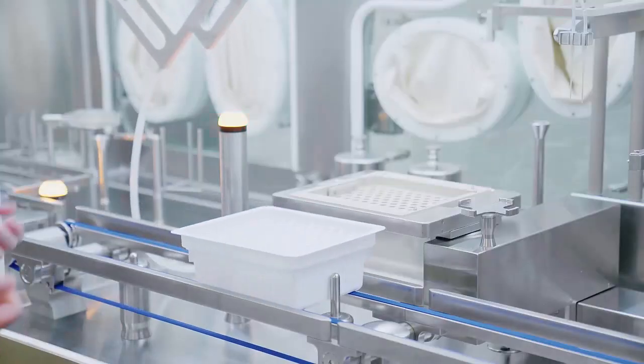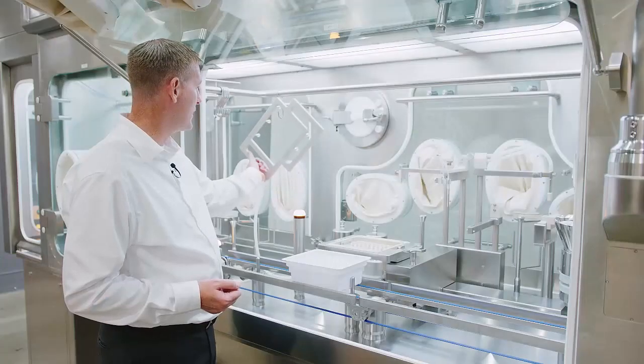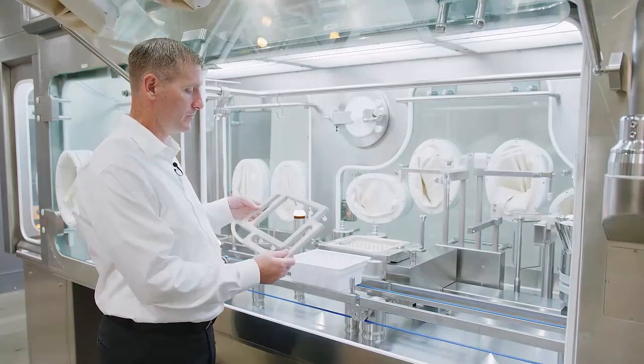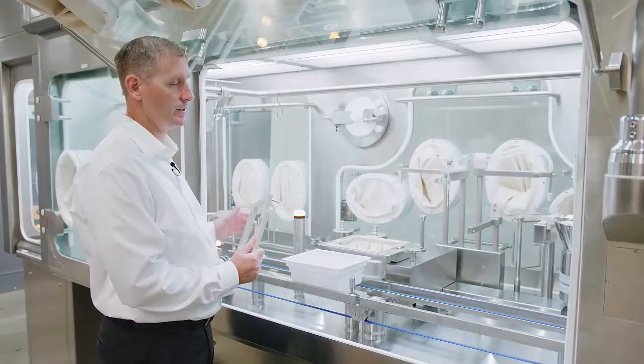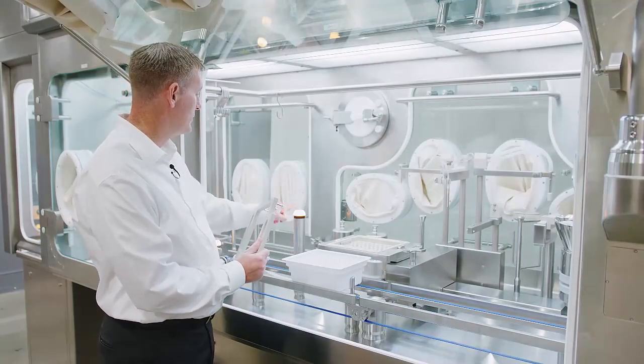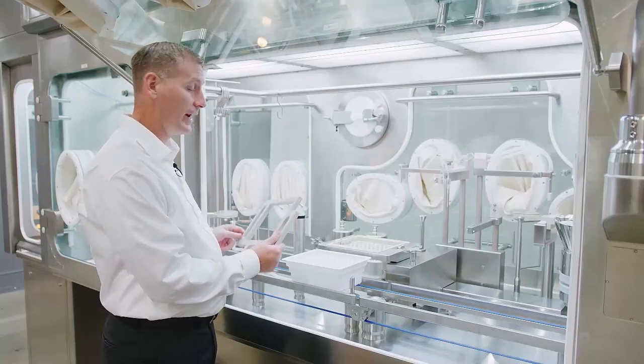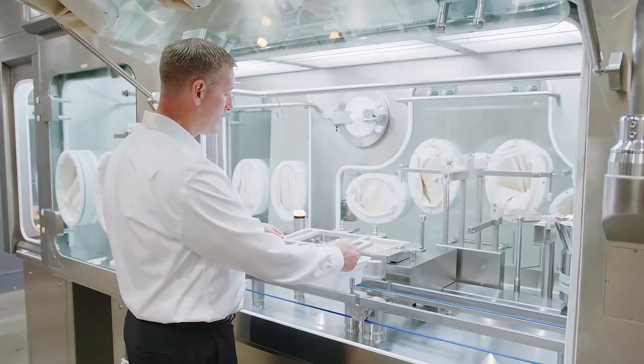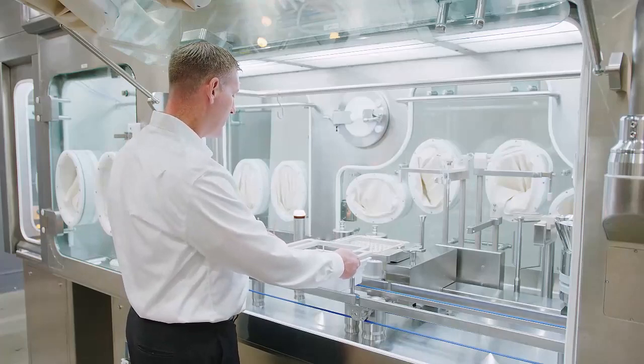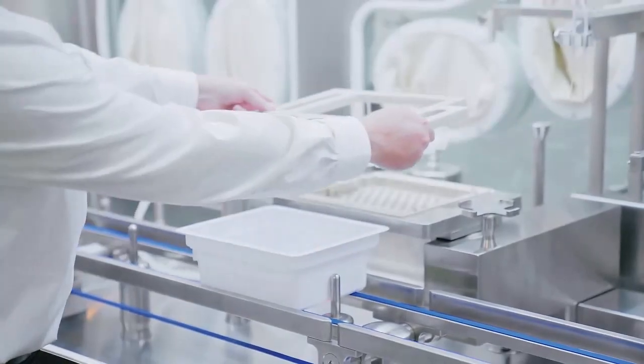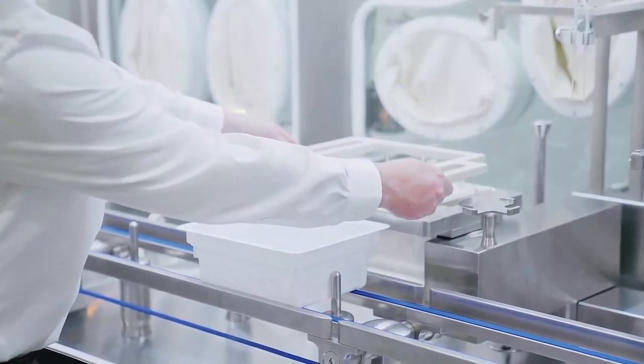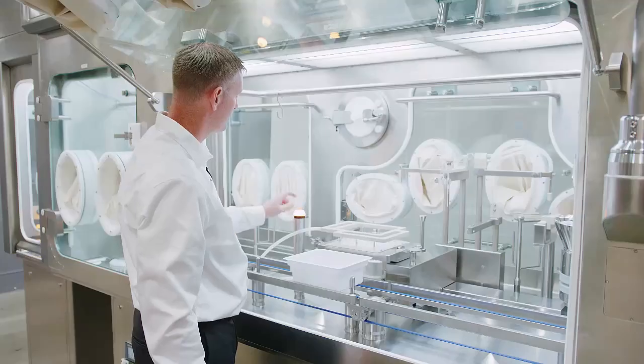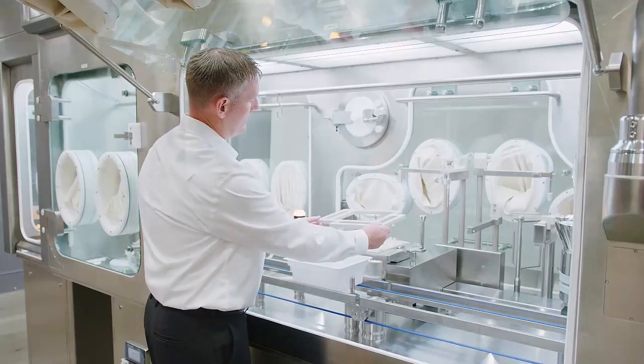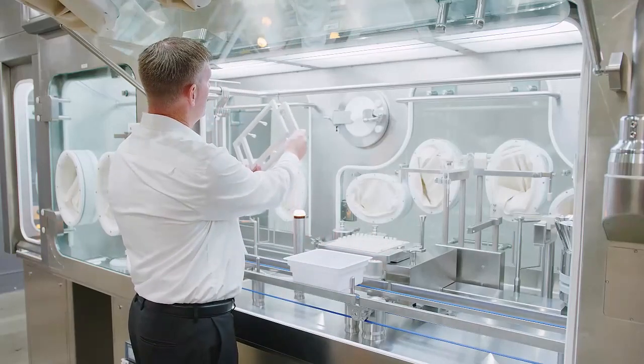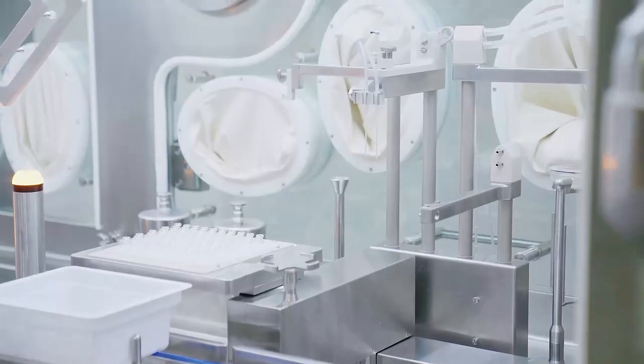Okay, so now that it's in position, it hits a tub stop, and then the operator will use this nest transfer tool that is specifically designed to ensure that we have good continuous airflow over the containers. Simply press the sensor quickly, which actuates the vacuum. The operator will then grab the nest and transfer the nest to the centering plate. Of course, this will be done via glove ports. Disconnect it, remove it, hang it onto the isolator, and then unglove.